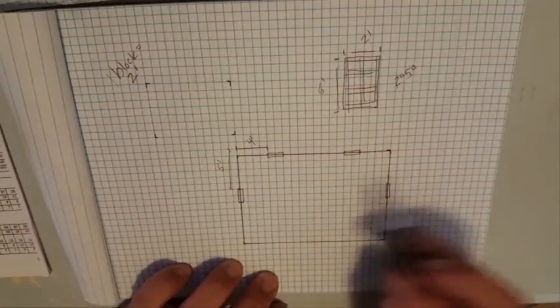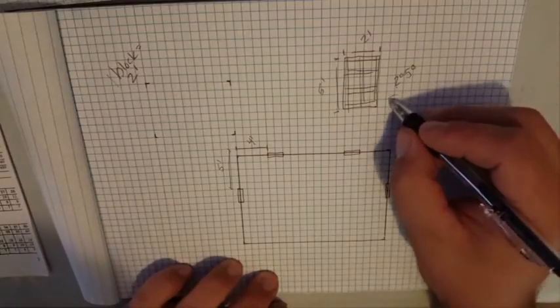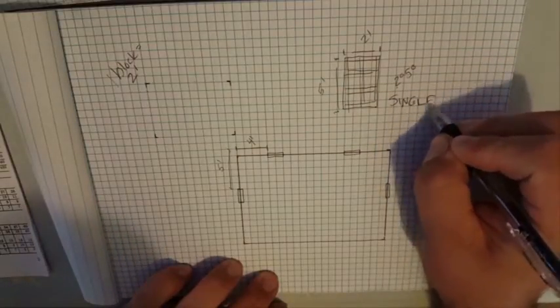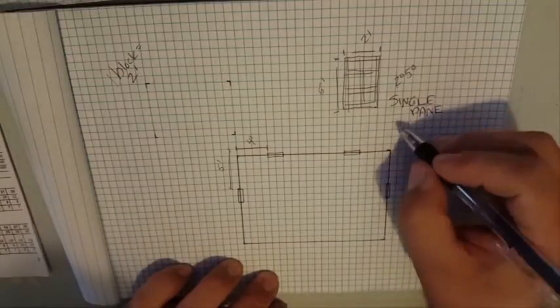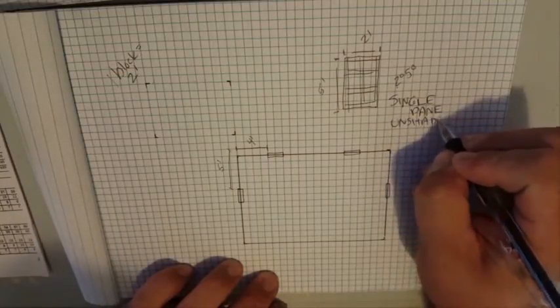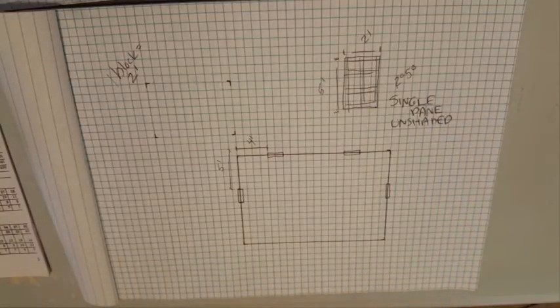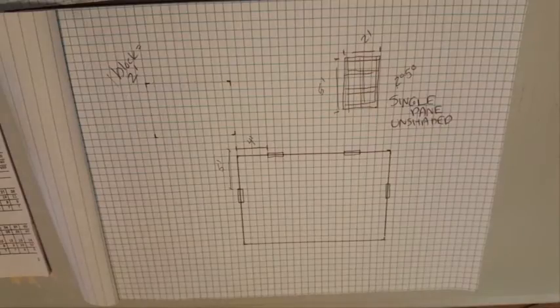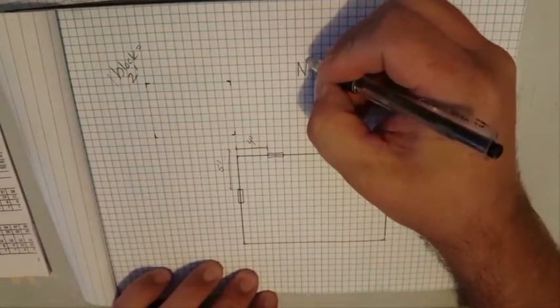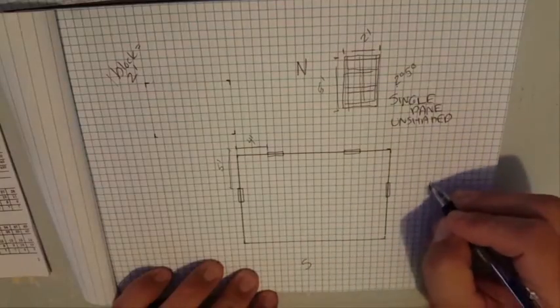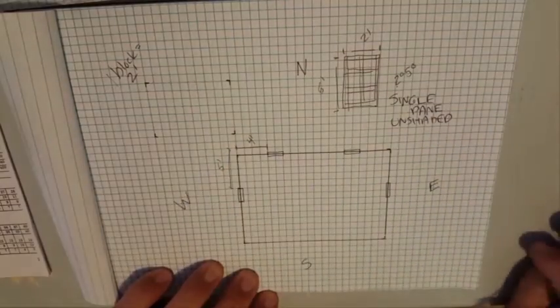Okay, so there's our four windows, remembering they're going to be single pane and let's say they're unshaded. Unshaded just means no blinds, no trees. If a window is facing a tree, it's similar to it facing north since it doesn't get any direct sun. We'll say this direction here is north, obviously then that's south, east and west. Our biggest load is on our east-west glass. The least amount of load is going to be on our northern glass.